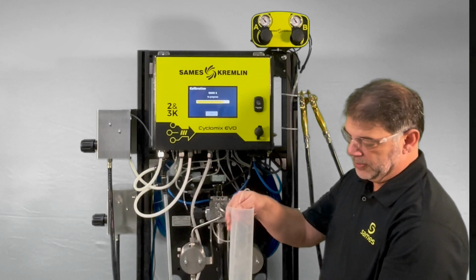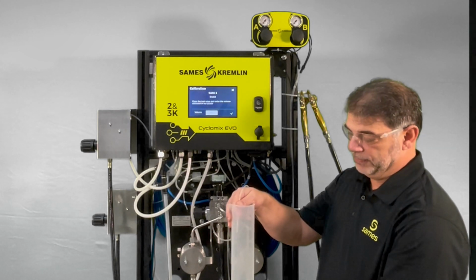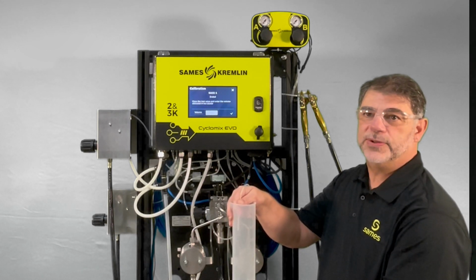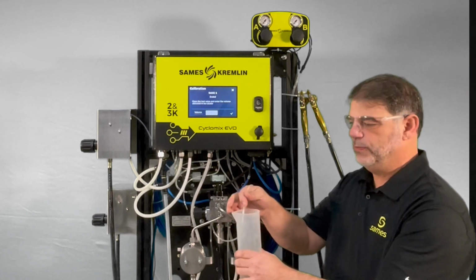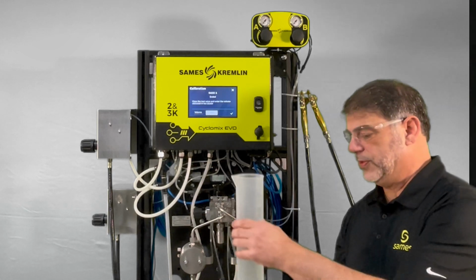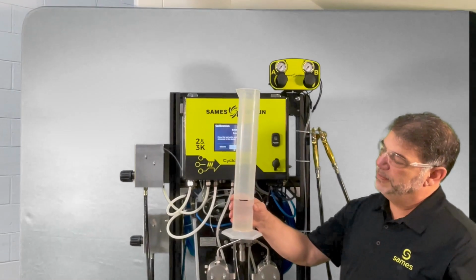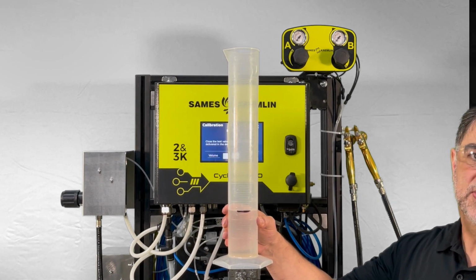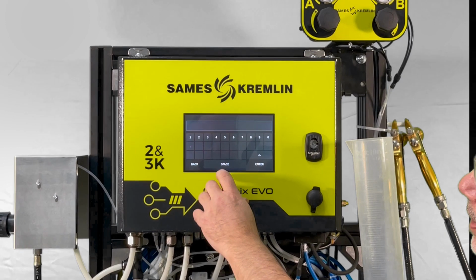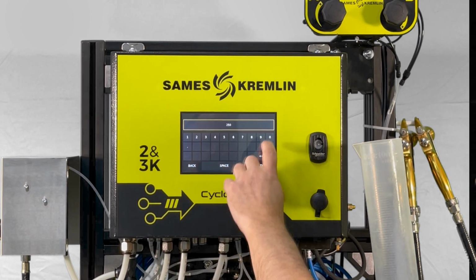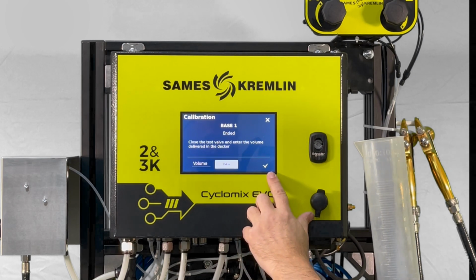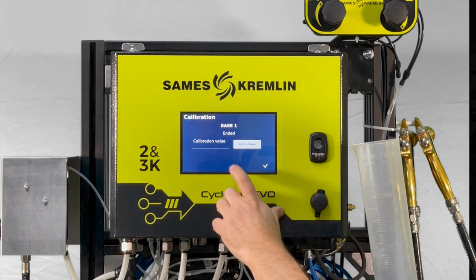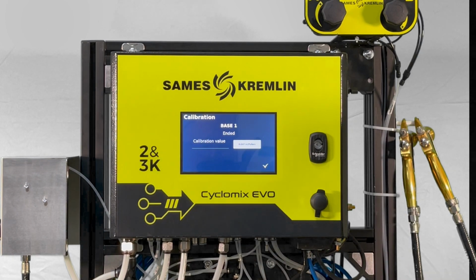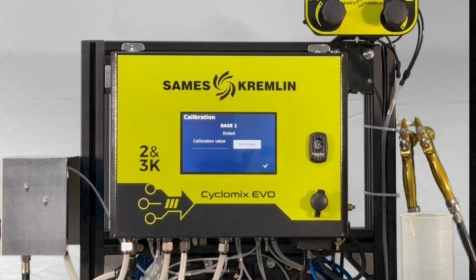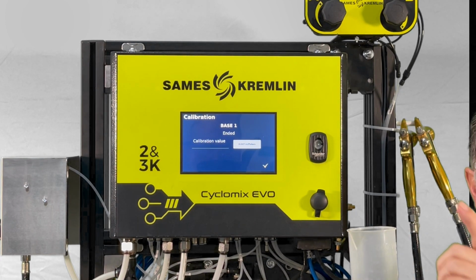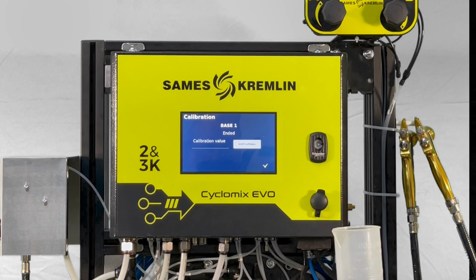It's going to run until it gets 1,000 pulses from the flow meter, which this flow meter should be around 0.24, so that should give us around 240, 250 cc's. So if we look at the beaker there, you can see we're right at about 250. So I'll enter that value here. And then go over to the check mark, select that, and that's what it calculated out to, 0.24 cc's per pulse.